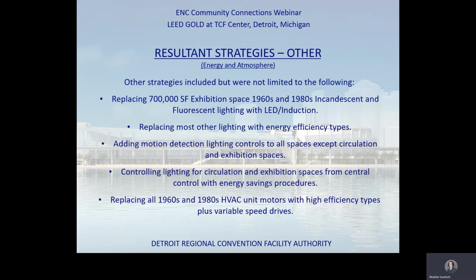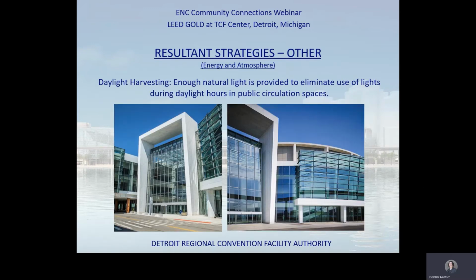Motion detectors were added to the lighting controls of most spaces, except exhibition and circulation areas, which became computer controlled. The 1960s and 1980s heating and ventilating unit motors were replaced with high efficiency ones and variable speed drives. Daylight harvesting was used extensively to allow public circulation lighting to be off during daylight hours.